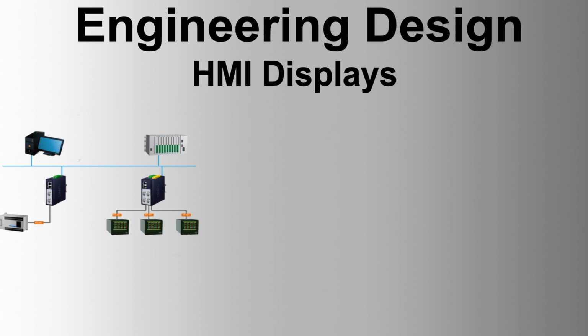Graphic title, preferably in the upper left corner of the screen. Navigation targets, consistently positioned to allow natural progression from one screen to another. Command zones, reserved for instrument faceplates or change zones to enable control changes by the operator. Information flow. Screens should be organized to allow natural progression from one area to another, typically from left to right and top to bottom. Layout for process scheme displays.